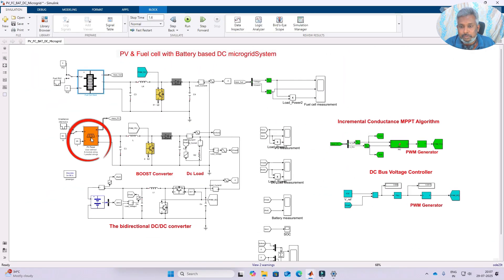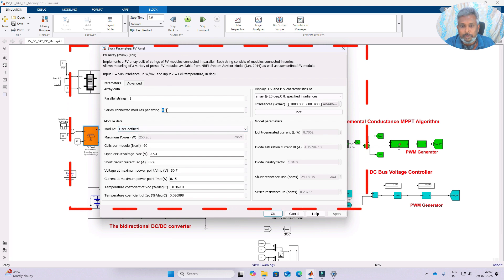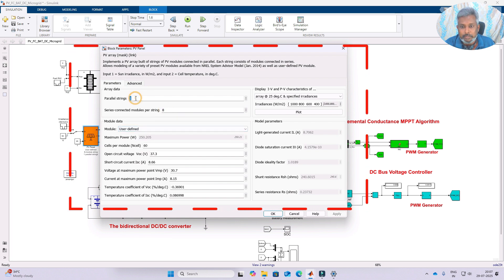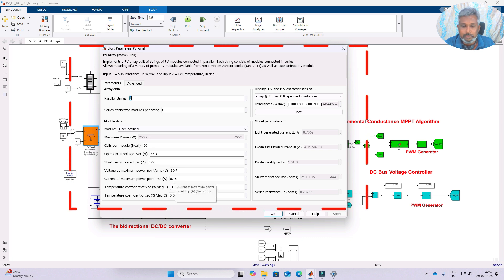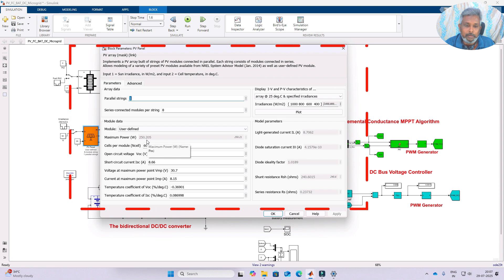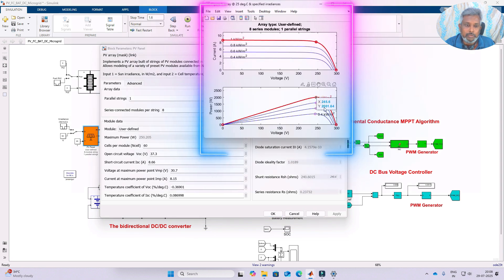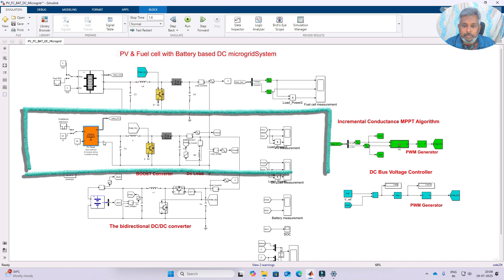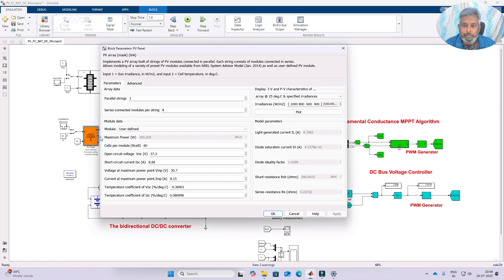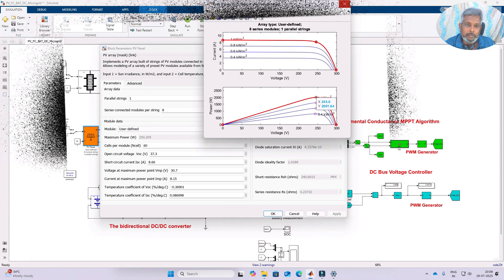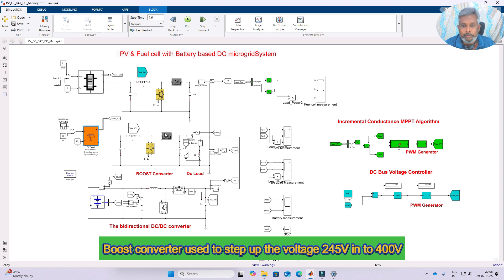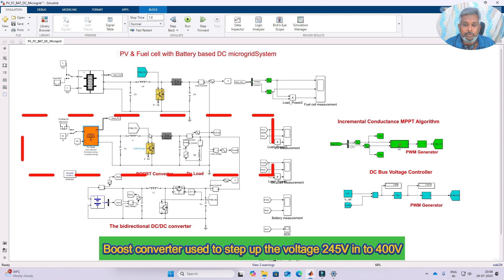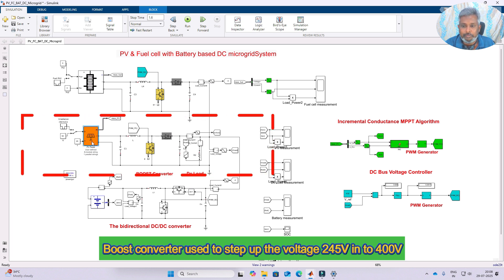Next is the PV panel. This PV panel has 8 series connected modules, 1 parallel string, and a single module rating of 250 watts. Voltage at maximum power point is 30.7 V and current at maximum power point is 8.15 A per panel. Total power generation is around 2000 watts at standard test condition — 1000 watts per square meter and 25 degrees Celsius. The PV is connected to the DC bus via a boost converter, with the PV voltage coming to around 245 volt, which is then boosted to 400 volt. This boost converter also works with the MPPT algorithm to extract maximum power from the PV panel.